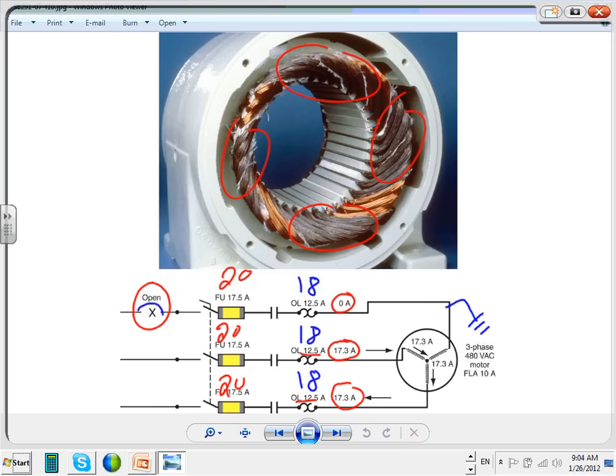Absolutely. Yeah, I assume it's superior to three independent fuses. Yes, because if you have a ground fault on a fuse, it will take one fuse. You're absolutely right. If I have a ground fault on a fuse, that fuse will burn, done, but these are still up and running, so I single phase. Again, single phasing. But guess what's going to protect you from single phasing though? The overload. Any question guys about overload?